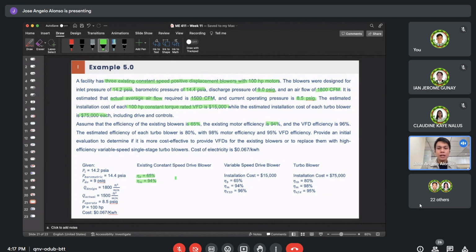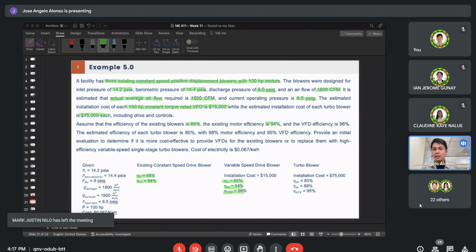For the frequency drive case, when we install a frequency drive, we still have the existing blower and existing motor since we didn't replace them. However, we only install a VFD. The efficiency of our VFD is 96%. And the installation cost, let's list it here, is $15,000.